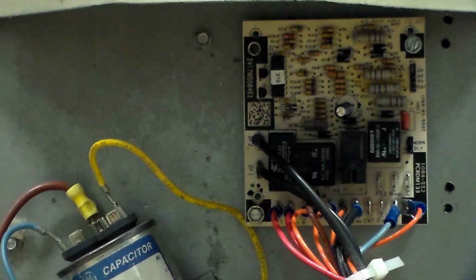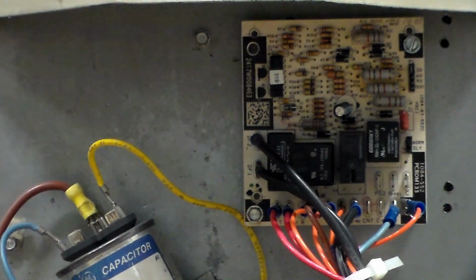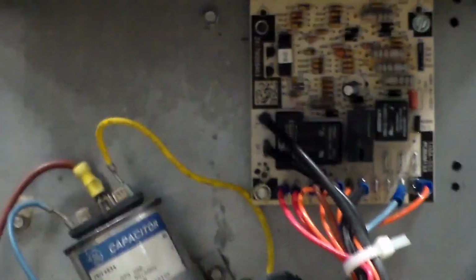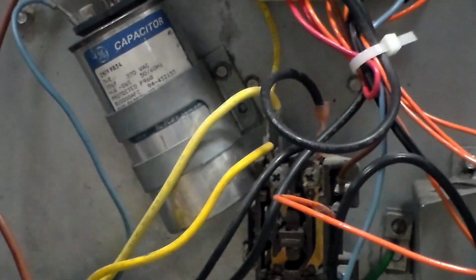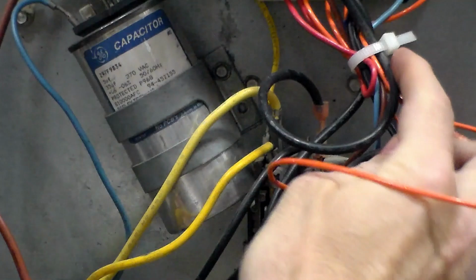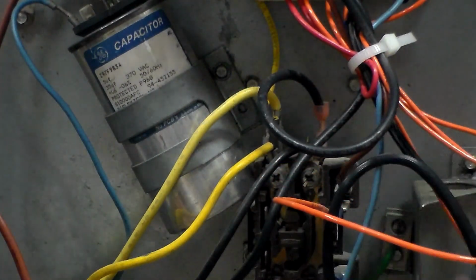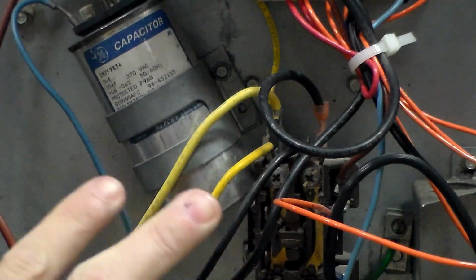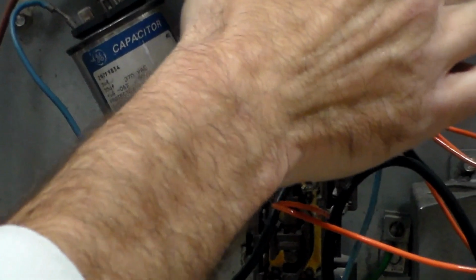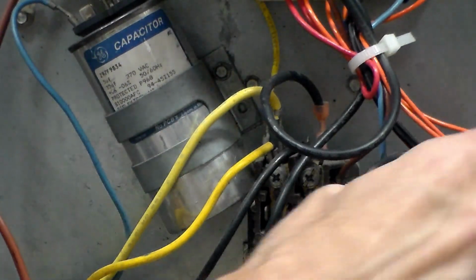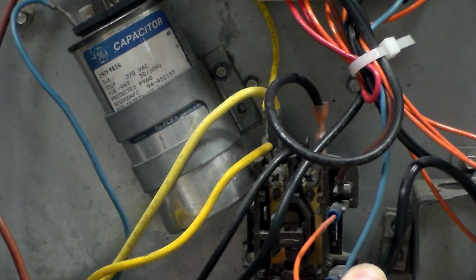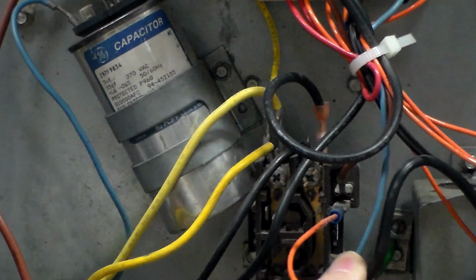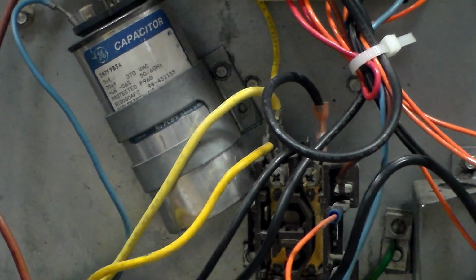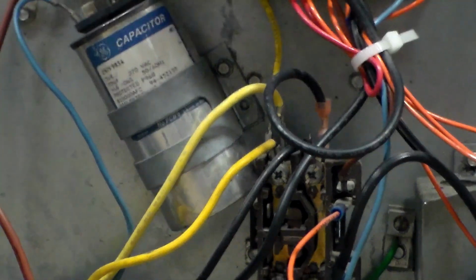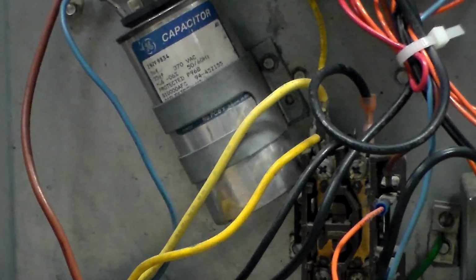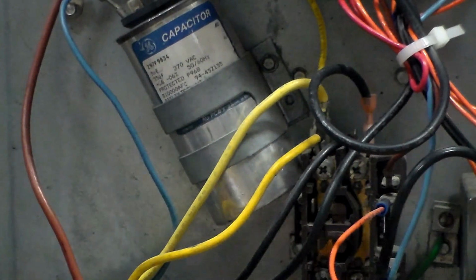So let me come down a little bit so you guys can see that. It's coming out on this cable here from the board out the O terminal. Instead of the other board having 2 terminals for the reversing valve, this one just has the 1, and it sends that O out through this cable to the reversing valve, and then the reversing valve comes back and terminates right here next to common on the contactor. That's very common, like a Goodman thing that I see a lot on Goodman. So instead of having the 2 terminals for the reversing valve, it comes back to here.